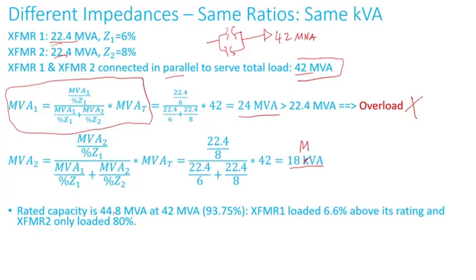One thing to note: the rated capacity of this substation — transformer one and two combined — is 44.8 MVA, and the load is 42 MVA, which is 93.75% of that capacity. Yet under this loading, which is less than the combined capability, transformer one is already loaded 6.6% above its rating. You can imagine if the load were increased to 44.8 MVA, transformer one's overloading would get even worse.